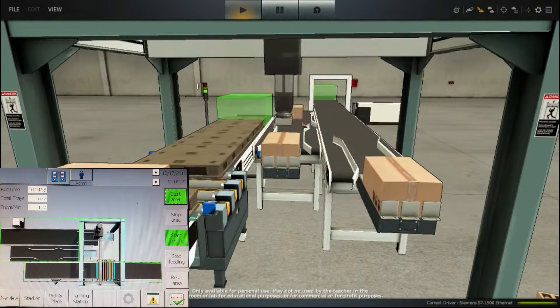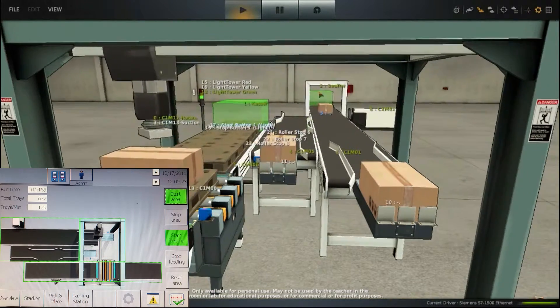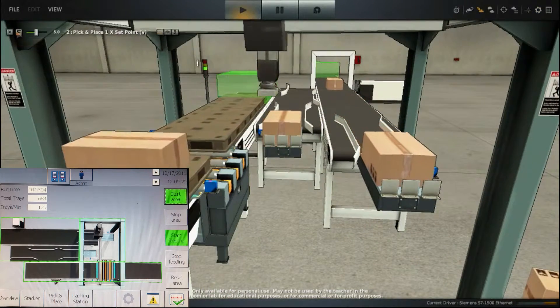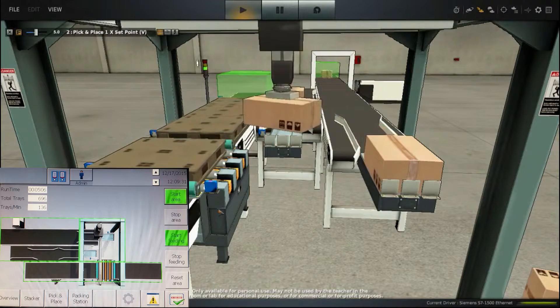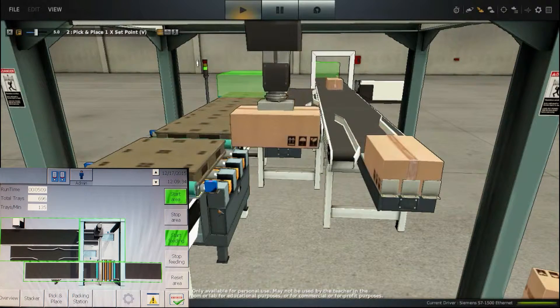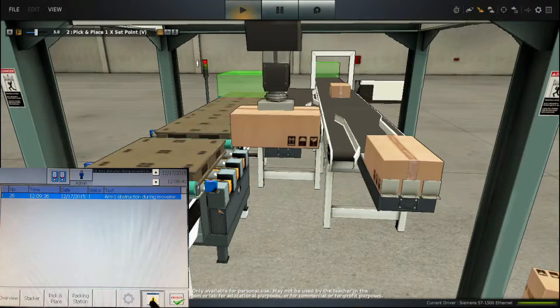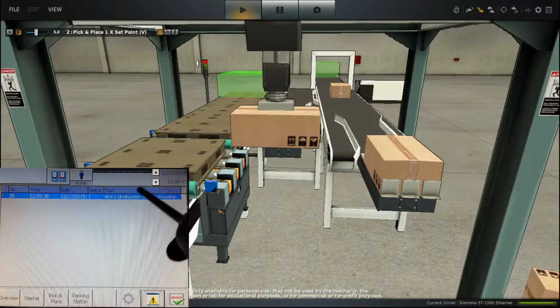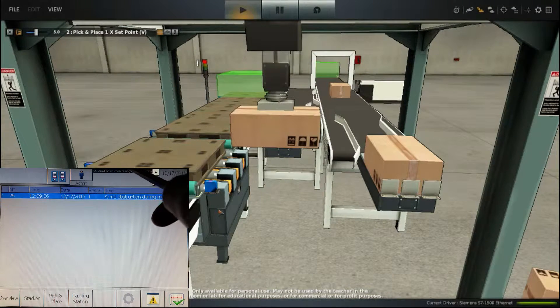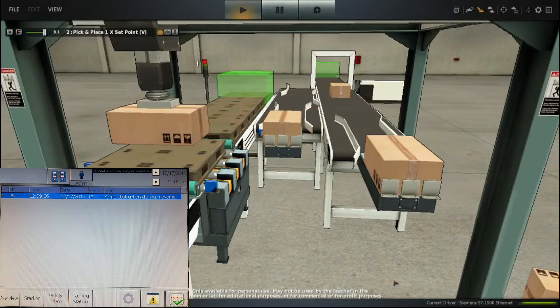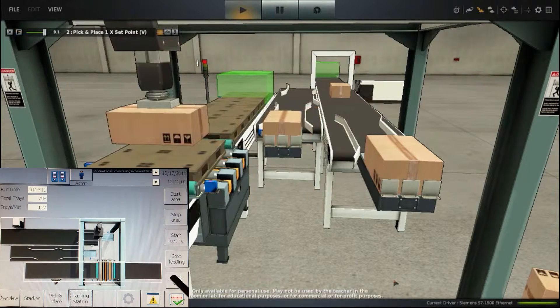We are able to force — let's say the X-axis here — and force it to be fixed, which means it will not be able to change the X variable on the pick and place. This will provide an obstruction error because the pick and place is not moving as expected. We see it here, and it is also shown at the top of the HMI. We can confirm it, remove the force, and then reset it on the PLC. Start the system, and the machine will carry on.